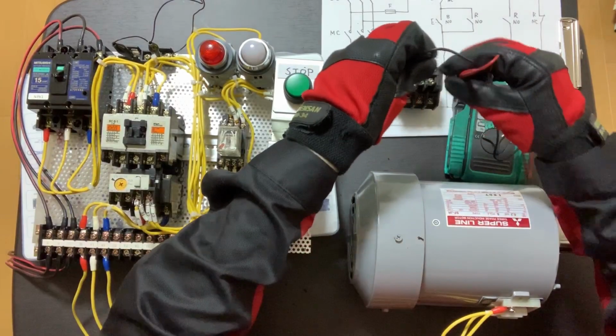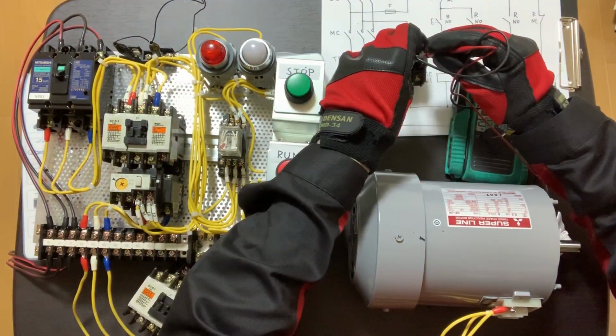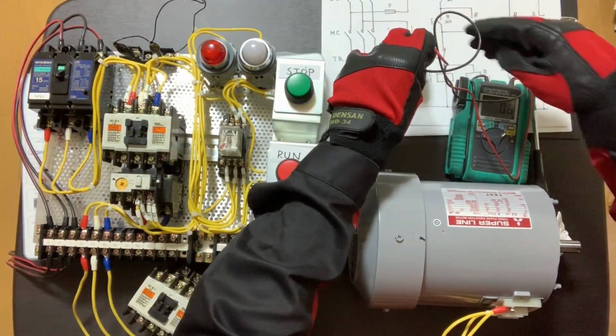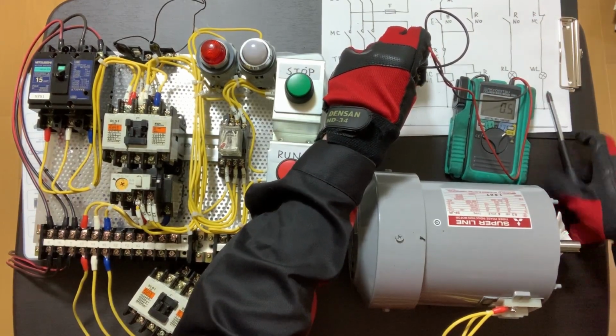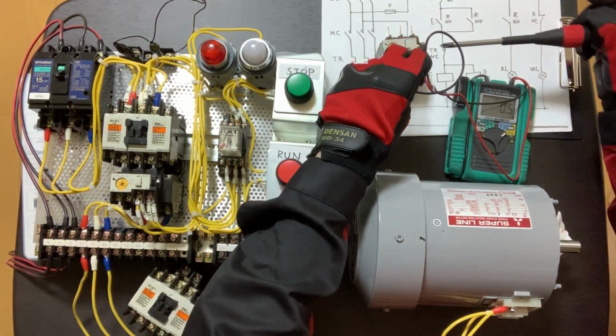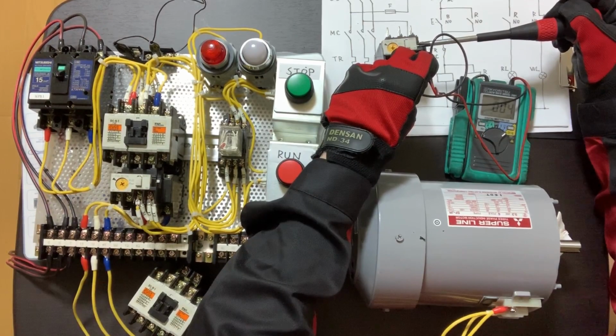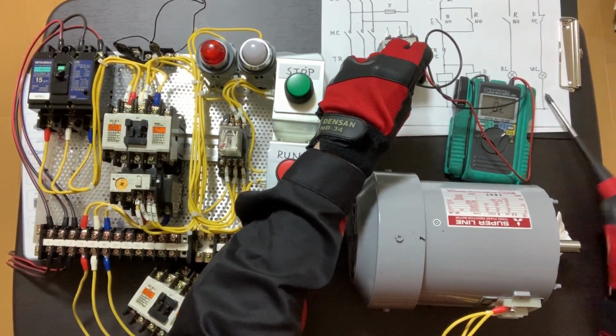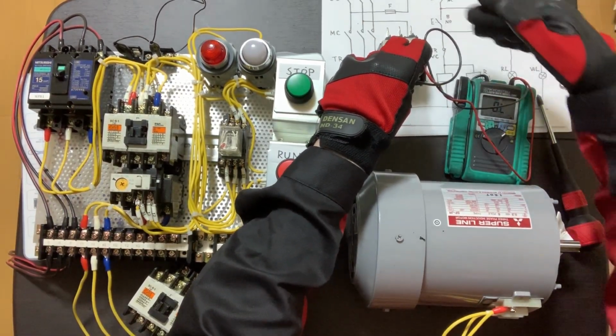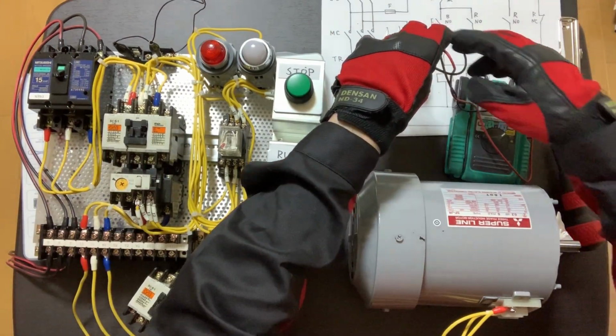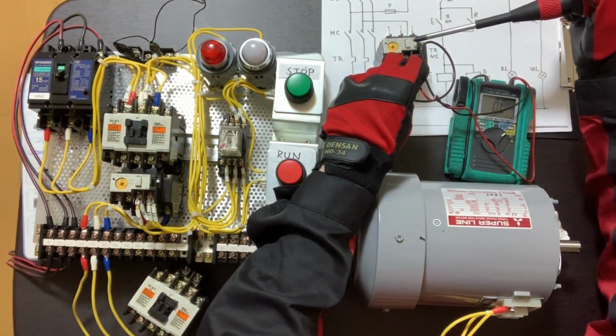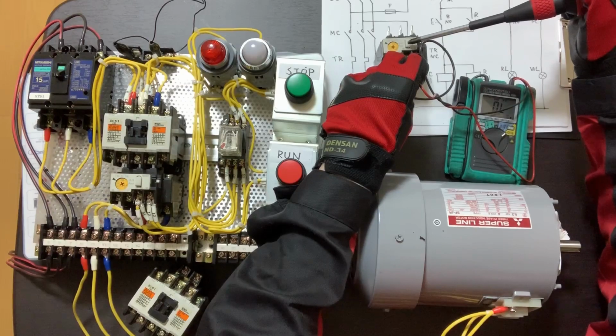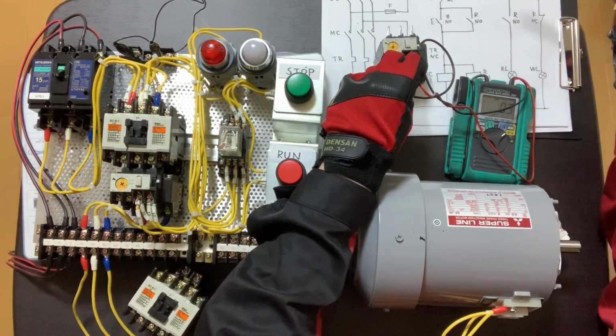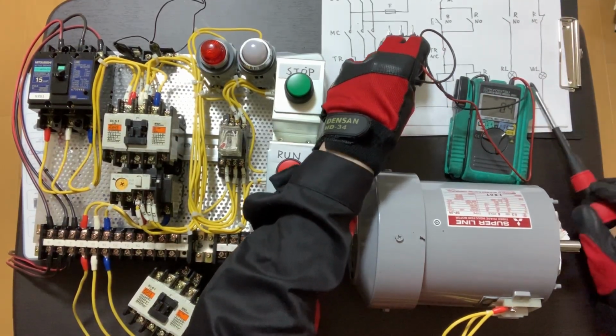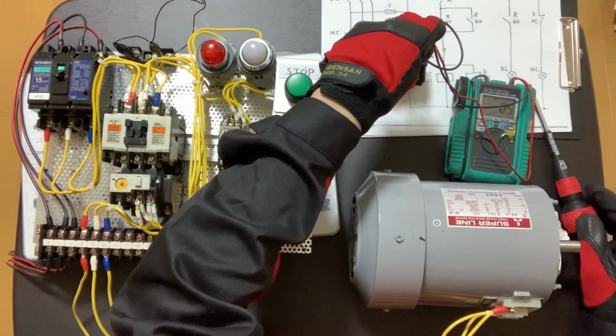So this is a normally closed contact, but if I push this test button, it turns to open. It's the same as the actual operation of the thermal relay. And if I push this reset button, it's reset, so it turns to the original state.